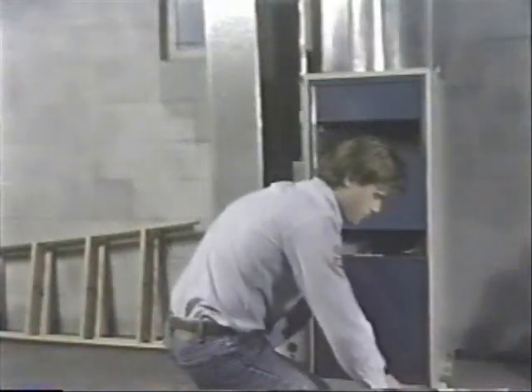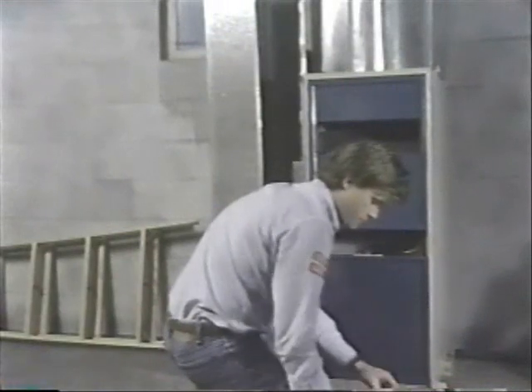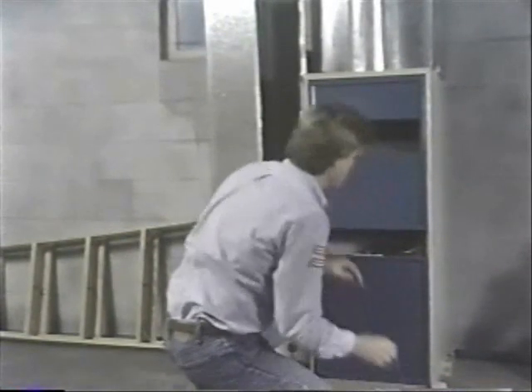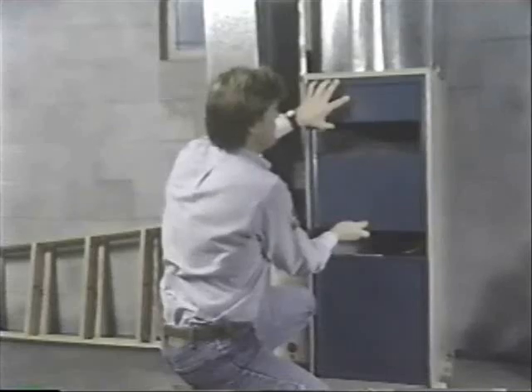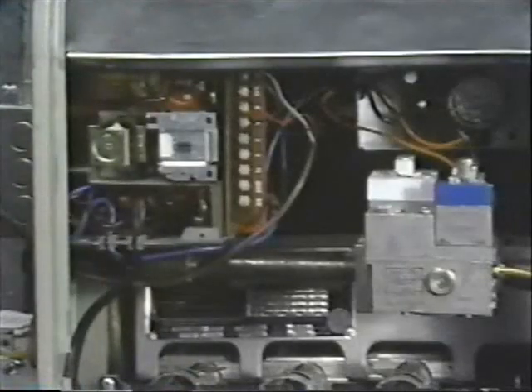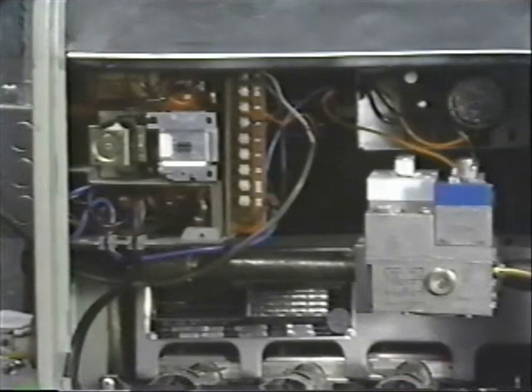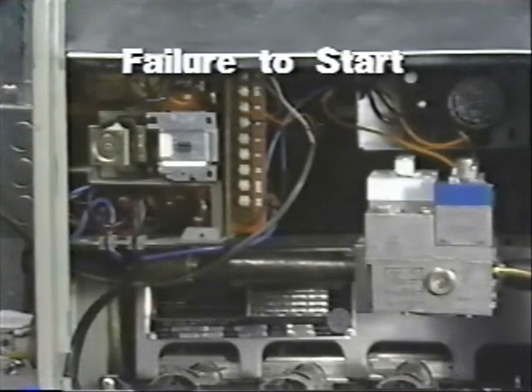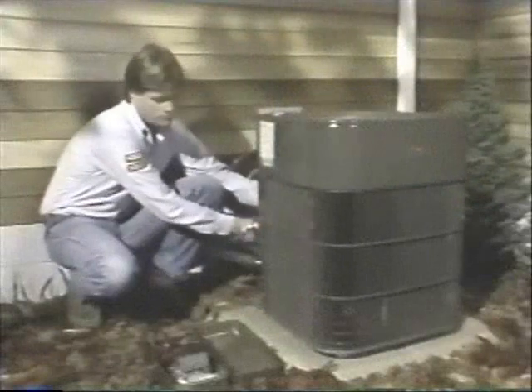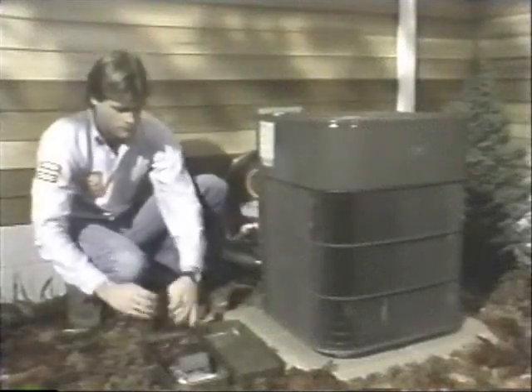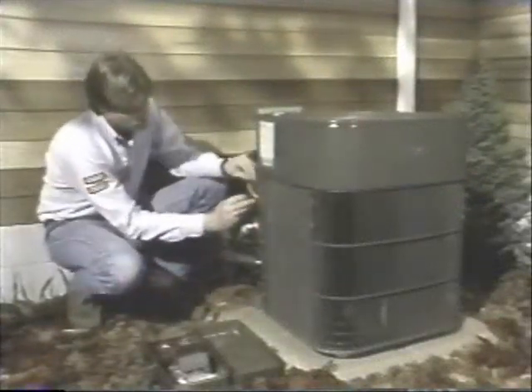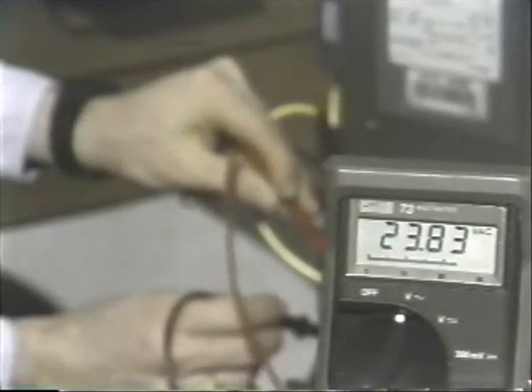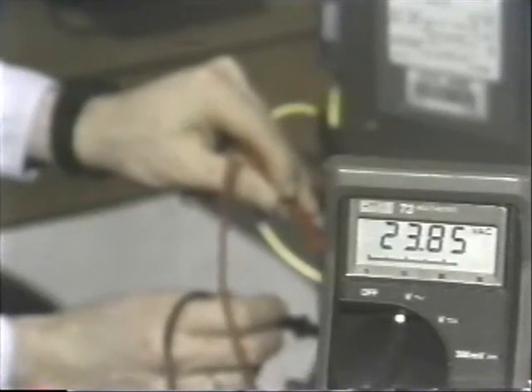Now that you have a better understanding of Class 2 control circuits and the various transformers that can be used in them, let's look at how to troubleshoot possible transformer problems in an air conditioning control system. In our first example, we'll assume that the system has failed to start. Check to see if the contactor has pulled in. If the contactor is open, check the voltage at the coil. If it won't pull in with the proper voltage in the coil, the contactor is bad and must be replaced.